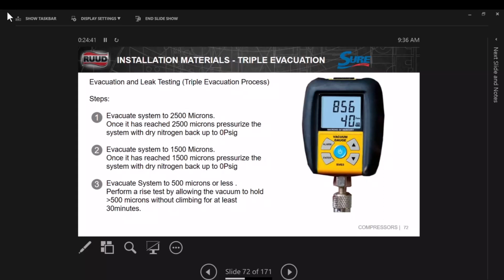Well, we're going to do a triple evacuation. Doesn't take long to do, because the first step is just pull down to 2,500 microns. That's nothing. Okay? And then once we reach 2,500, we're going to break it with nitrogen. And we're going to pull it down to 1,500 microns. We're going to break it again with nitrogen. And then we're going to pull our 500 micron vacuum. So each time we do that, we're getting more moisture out. We're putting dry nitrogen in, which is drying it out, pushing that moisture back out. And now, when we pull down to this 500 microns, you're not going to see your gauge come up much. Maybe a little bit, but not much.